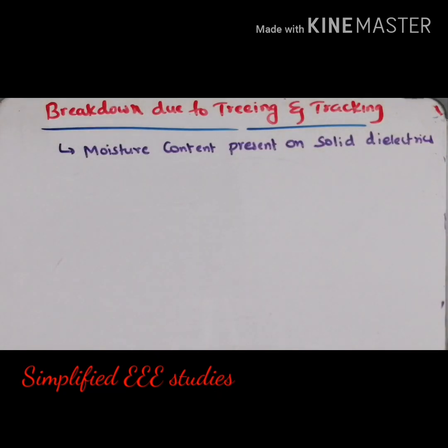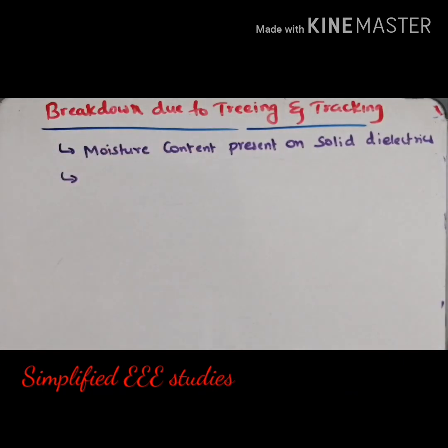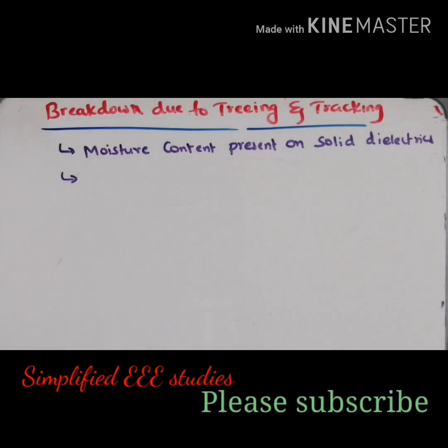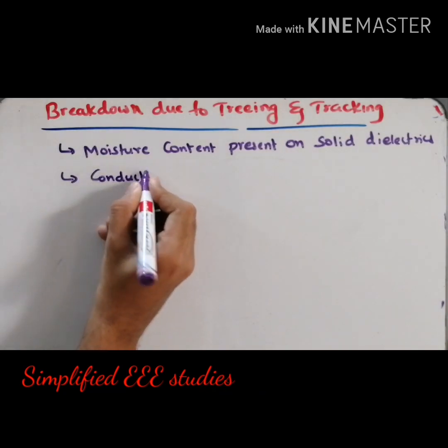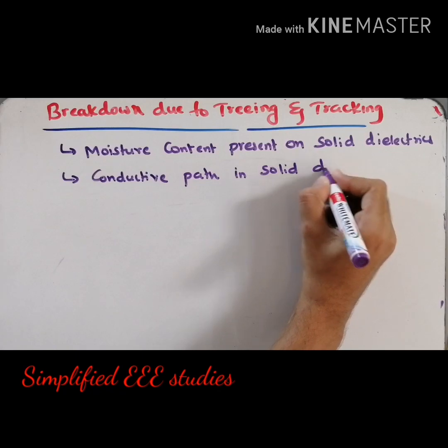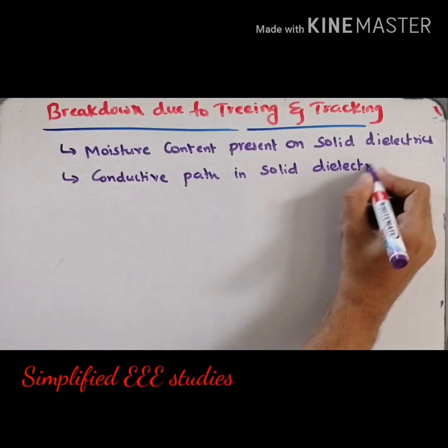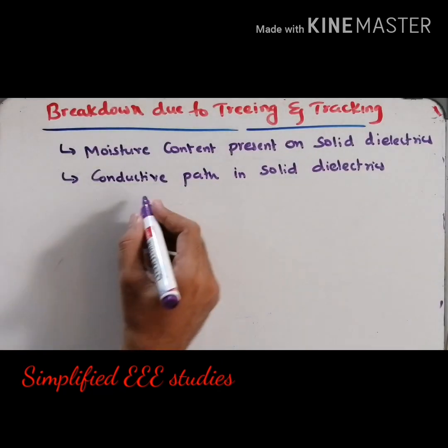Suppose if you are operating a solid dielectric material under the presence of moisture or water content, this phenomenon occurs. Because of this moisture content, slowly some amount of conductive path will be developing inside the solid dielectric material. This may result in the treeing and tracking phenomenon.